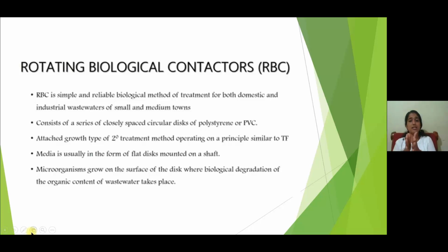It consists of a series of closely spaced circular discs of polystyrene or PVC, that is polyvinyl chloride, and is an attached growth type of secondary treatment method operating on a principle similar to that of a trickling filter. The media is usually in the form of flat discs mounted on a shaft. A shaft will be provided. On this shaft, circular discs are fitted parallelly, and the microorganisms grow on the surface of these discs, where biological degradation of the organic content in the wastewater takes place.